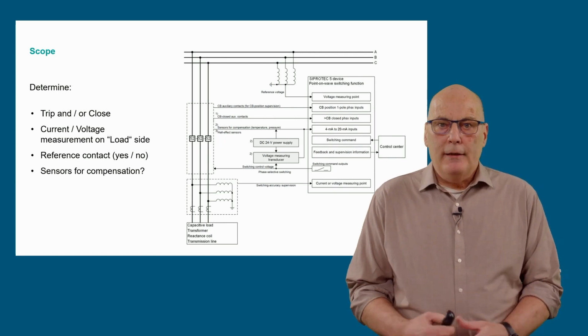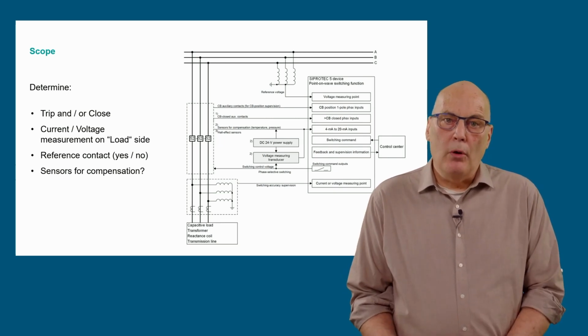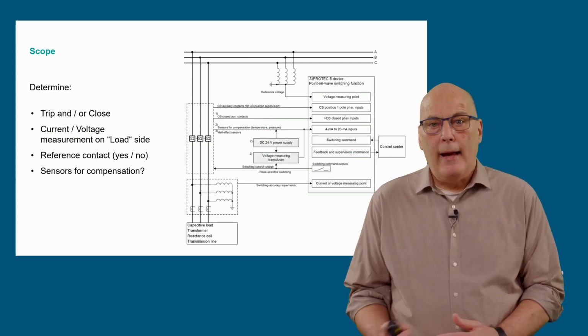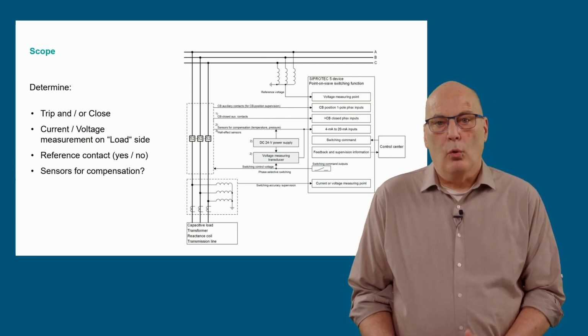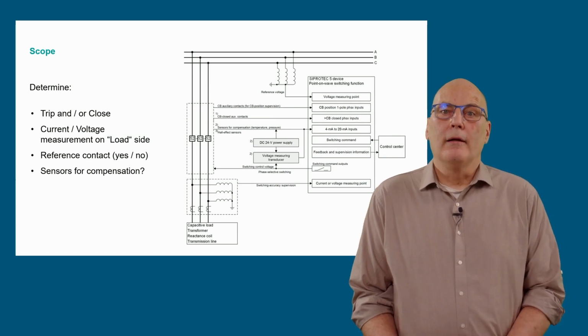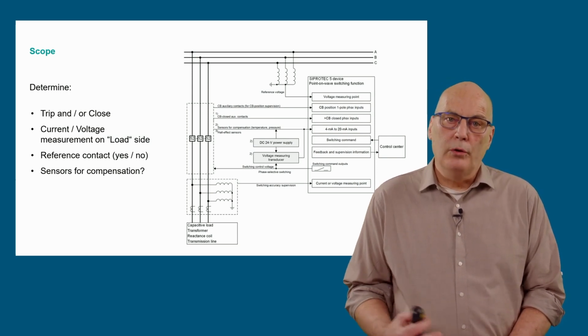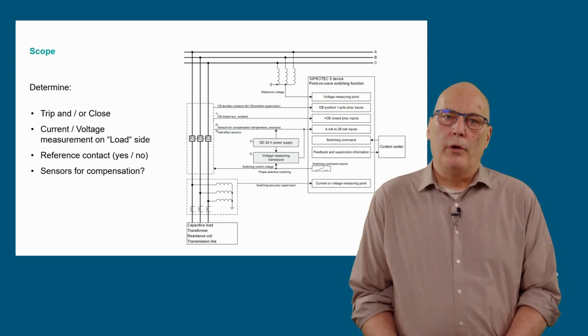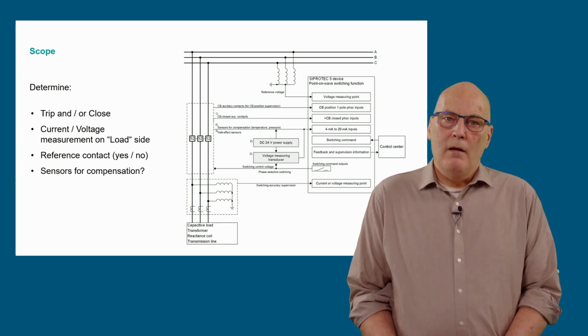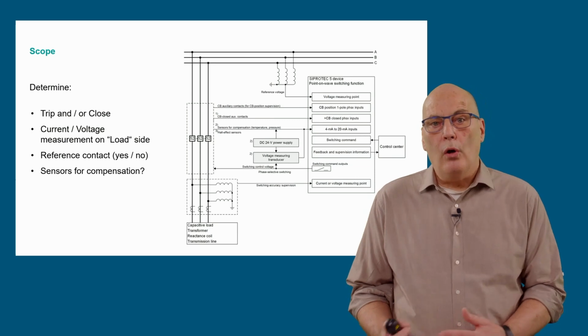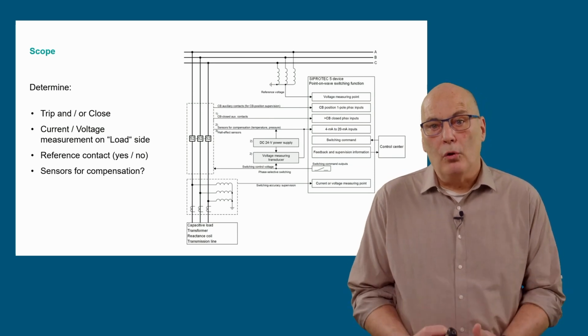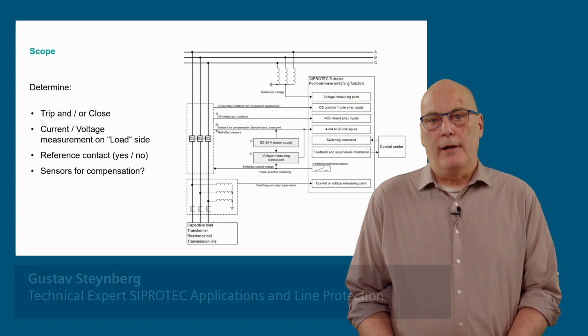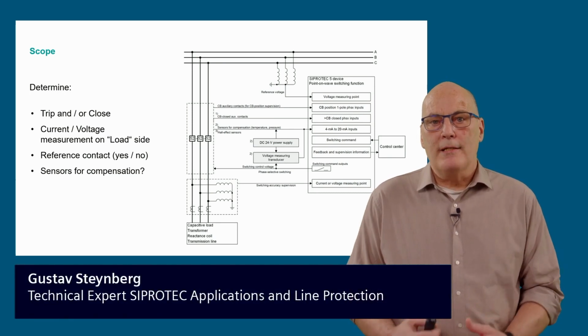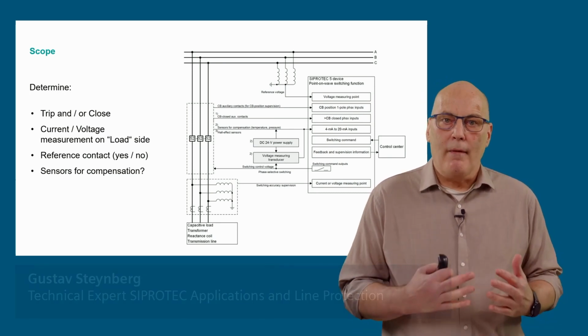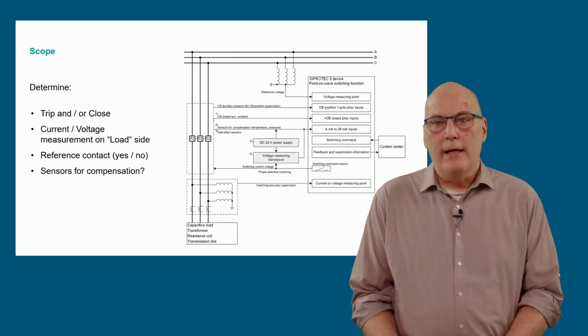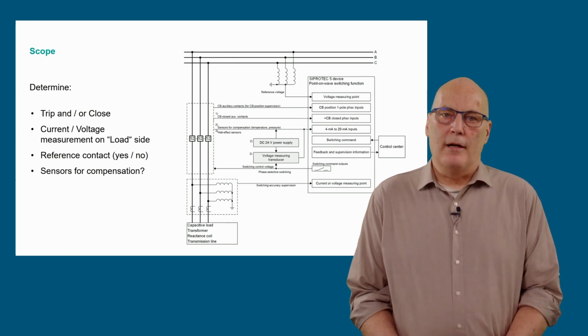It must be checked if the circuit breaker mechanical switching will be monitored with reference contact and transducer inputs, so-called Hall effect sensors, in the middle of the diagram, or alternatively via auxiliary contacts connected to binary inputs. Finally, the use or not of sensors for temperature, control voltage and hydraulic pressure must be defined. All of these decisions regarding the scope of supply are finalized. The device may then be selected as shown in the next slide.